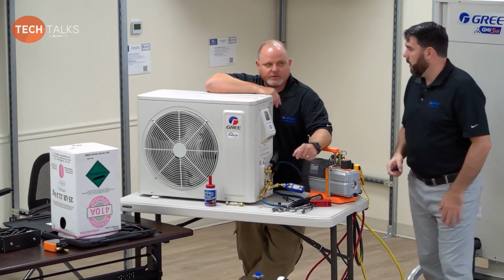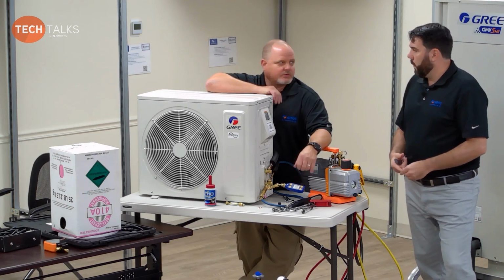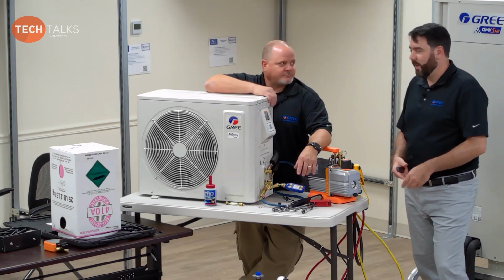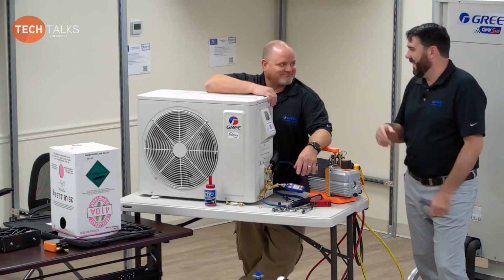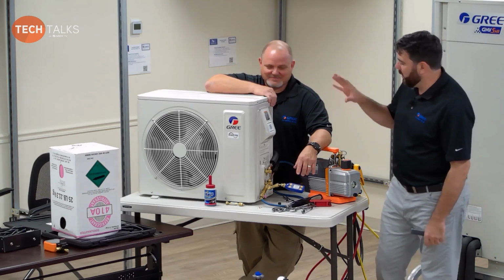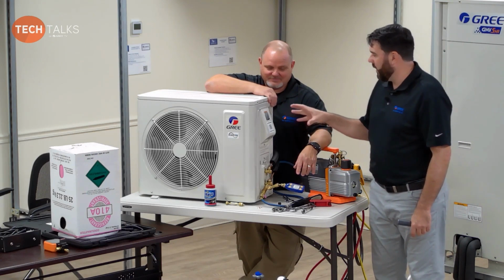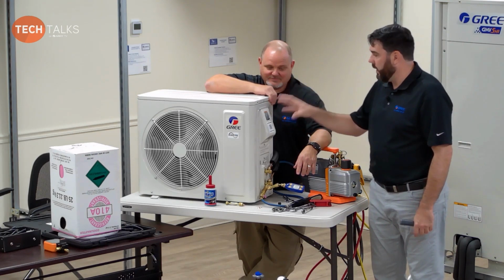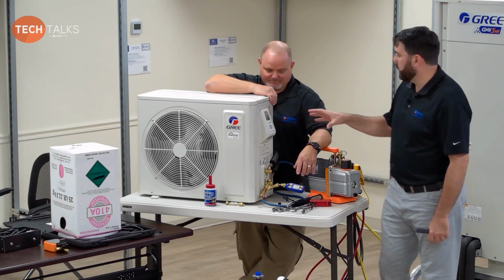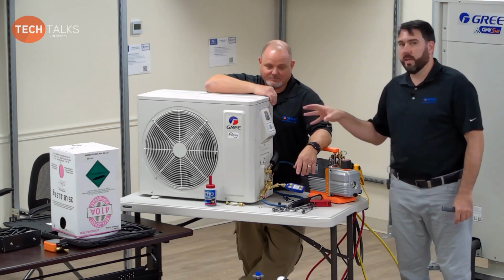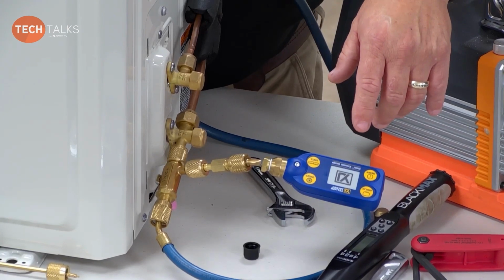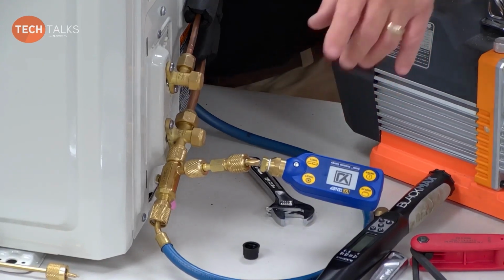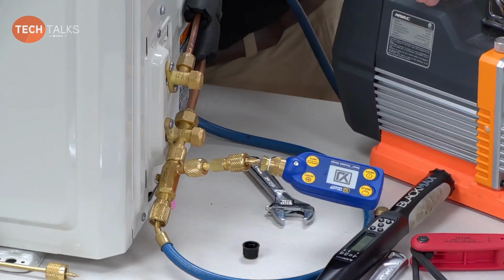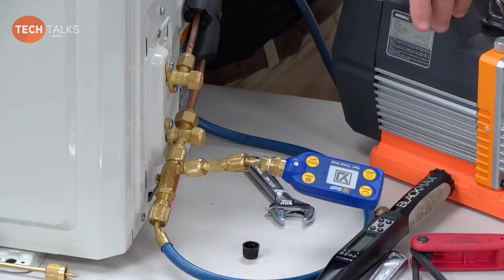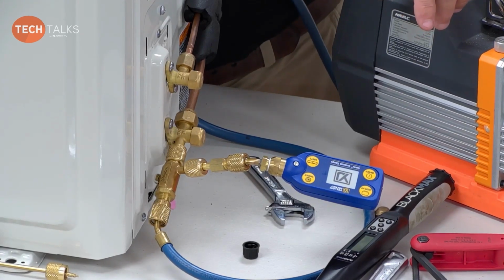It's interesting that you bring up cold weather like that. So what else should we be doing when it's that cold outside? You've got a really good point. Before we complete this process, and I would recommend it on any Gree system that we sell, you power this thing up for a minimum amount of time prior to starting it, so that the compressor crankcase heater has time to warm up the compressor, and then once we open our valves, we can get that liquid out of the compressor so we don't damage it when it starts up.